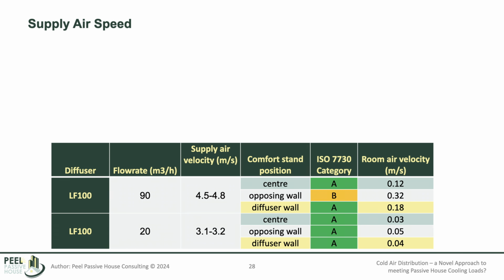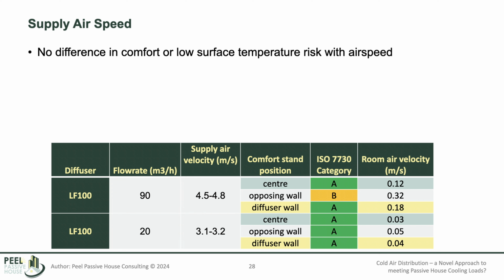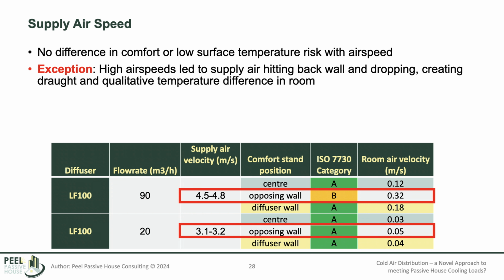Supply air speed generally didn't have an impact on comfort. The exception is when I had a really high speed, bordering on about 5 meters per second - in such a small room, it was hitting the back wall and then coming down and causing an issue. So you just gotta watch the airspeed depending on the size of the room.